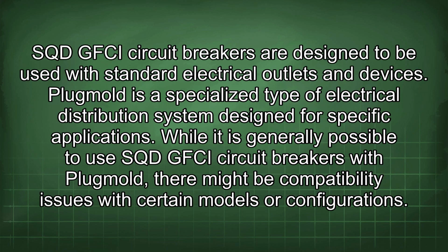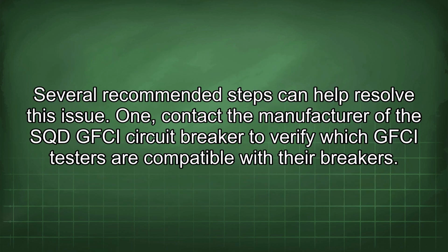SQD GFCI circuit breakers are designed to be used with standard electrical outlets and devices. Plugmold is a specialized type of electrical distribution system designed for specific applications. While it is generally possible to use SQD GFCI circuit breakers with Plugmold, there might be compatibility issues with certain models or configurations. Several recommended steps can help resolve this issue.